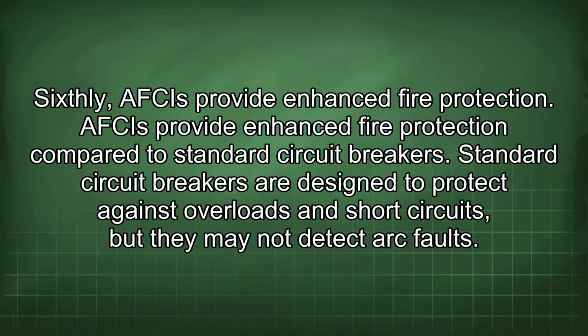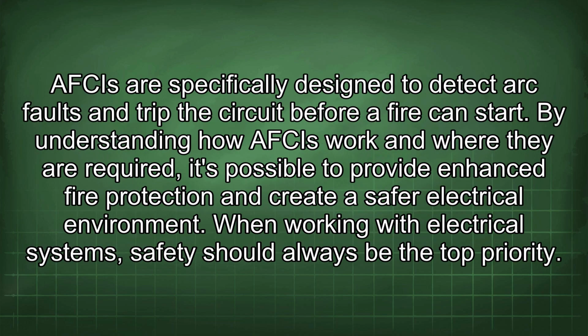Standard circuit breakers are designed to protect against overloads and short circuits, but they may not detect arc faults. AFCIs are specifically designed to detect arc faults and trip the circuit before a fire can start. By understanding how AFCIs work and where they are required, it's possible to provide enhanced fire protection and create a safer electrical environment. When working with electrical systems, safety should always be the top priority.